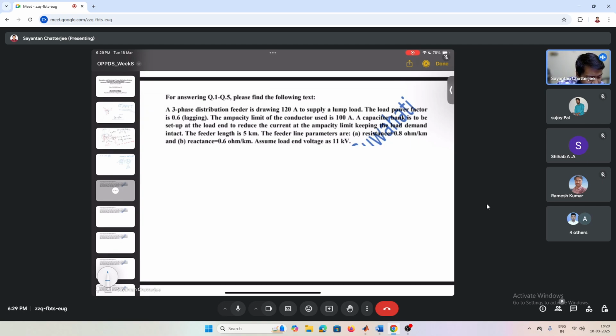A three-phase distribution feeder is drawing 120 amperes to supply a lump load. The load power factor is 0.6 lagging. The ampacity limit of the conductor is 100 amperes. A capacitor bank is to be set up at the load end to reduce the current to the ampacity limit, keeping the load demand intact - so the load demand remains fixed. The feeder length is 5 kilometers, and the feeder line parameters (resistance and reactance) are given per kilometer. The load end voltage is 11 kV. This is the problem statement with 5 questions to write down.